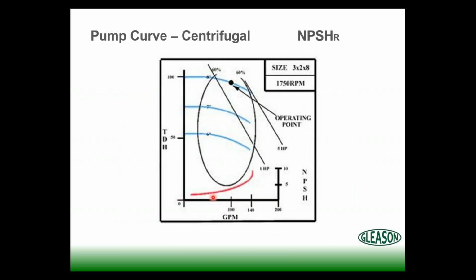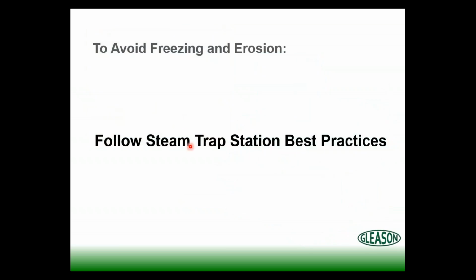Here's just another example. That red part is NPSH required for a different pump, different model number. One of the problems we see here is these standard units are rated to 180 degree water. And so if your condensate is hotter than that, then guess what? Our tank's not high enough. We don't have enough NPSH on the upstream side of the pump to keep it from cavitating. So we're going to have some cavitation problems there.